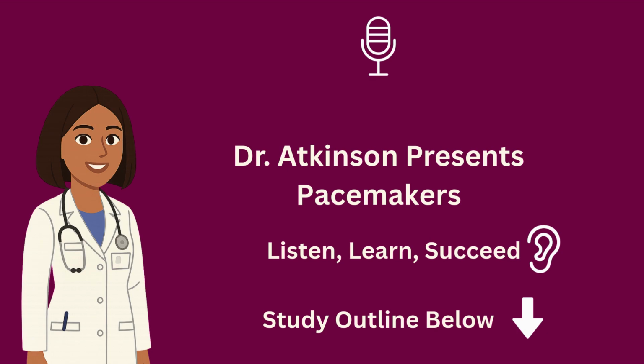Because pacemakers are used worldwide, a universal code system was developed to describe their function clearly. This is called the NASPE-BPEG code, named after the North American Society of Pacing and Electrophysiology and the British Pacing and Electrophysiology Group. The code consists of up to 5 letters. The first letter tells us which chamber is being paced: A for atrium, V for ventricle, and D for dual. The second letter tells us which chamber is being sensed: again, A, V, D, or O if sensing is turned off. The third letter describes how the pacemaker responds to what it senses: I for inhibited, T for triggered, D for both, and O for none.